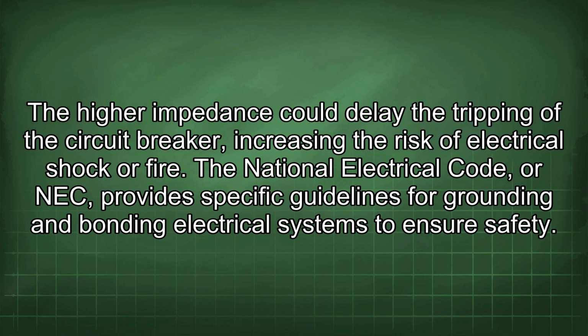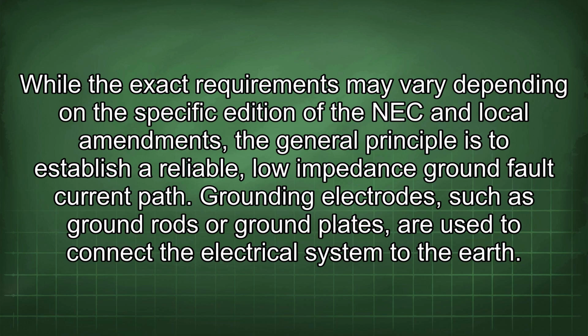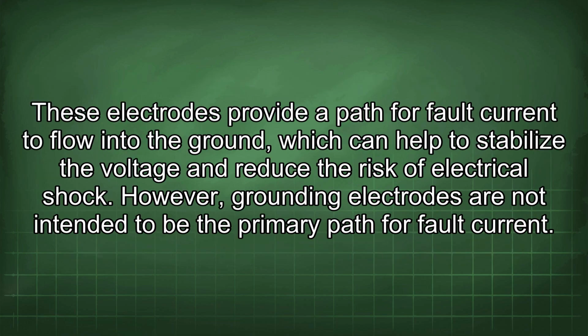The National Electrical Code, or NEC, provides specific guidelines for grounding and bonding electrical systems to ensure safety. While the exact requirements may vary depending on the specific edition of the NEC and local amendments, the general principle is to establish a reliable, low-impedance ground fault current path. Grounding electrodes, such as ground rods or ground plates, are used to connect the electrical system to the earth. These electrodes provide a path for fault current to flow into the ground, which can help to stabilize the voltage and reduce the risk of electrical shock.